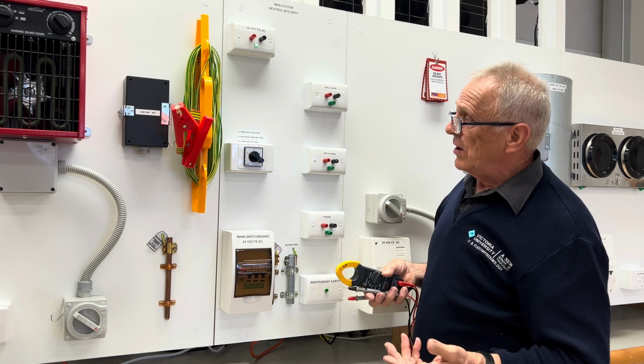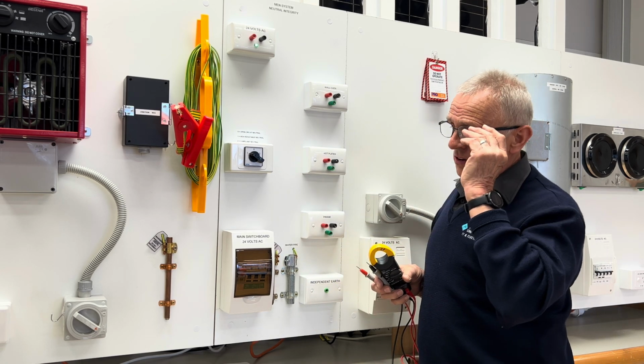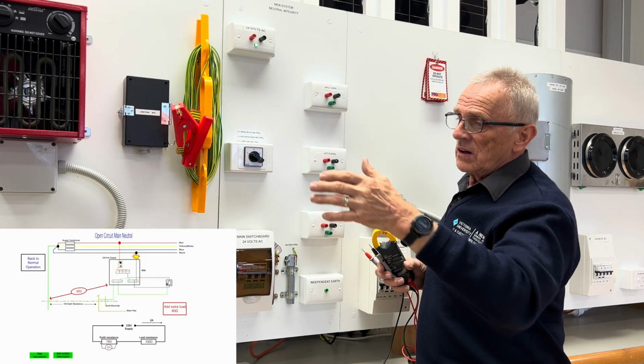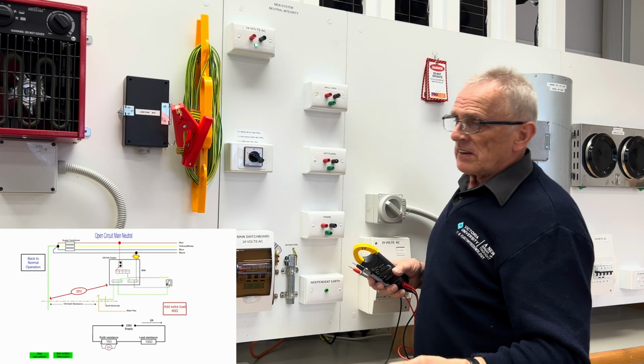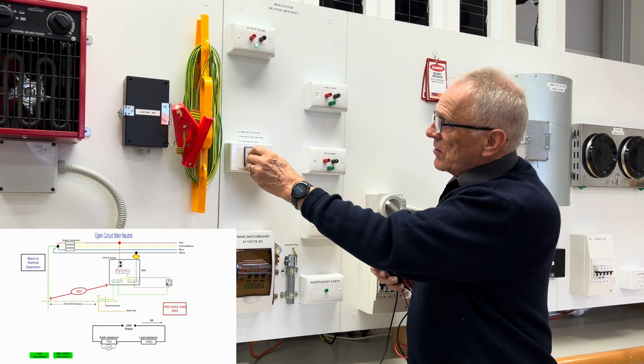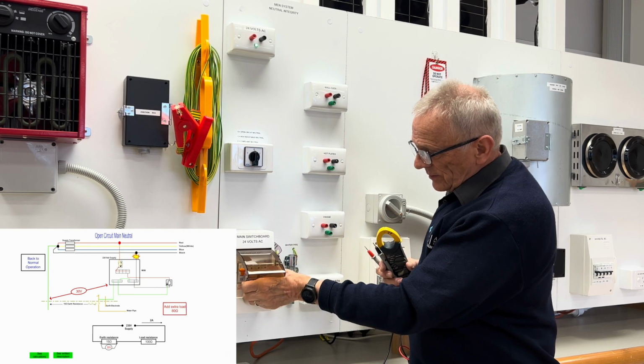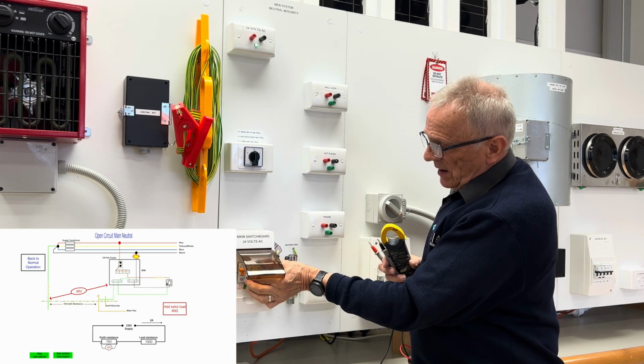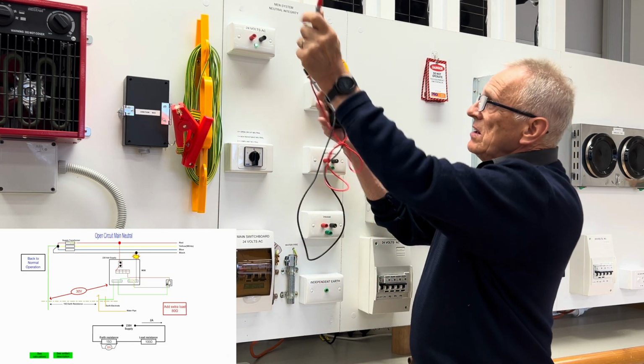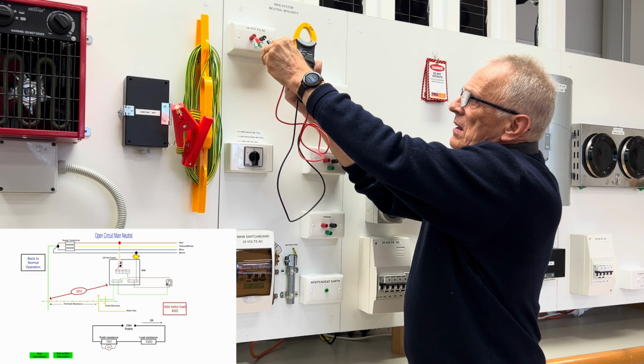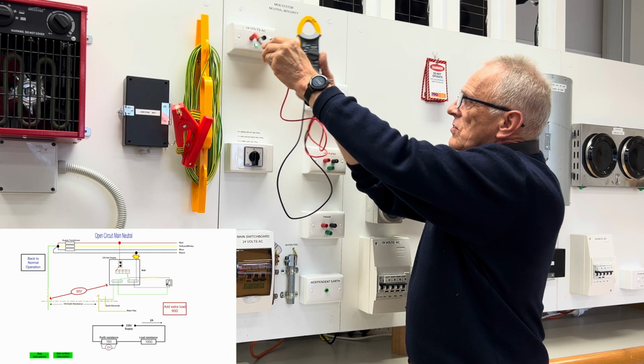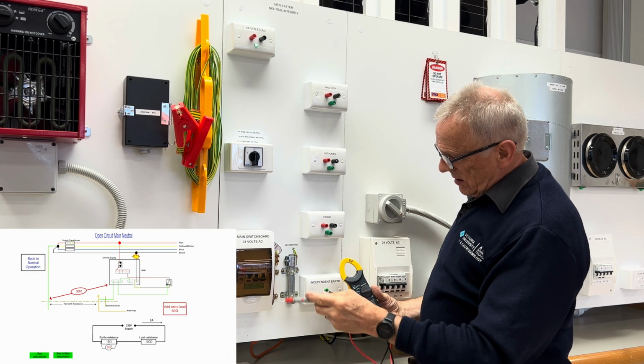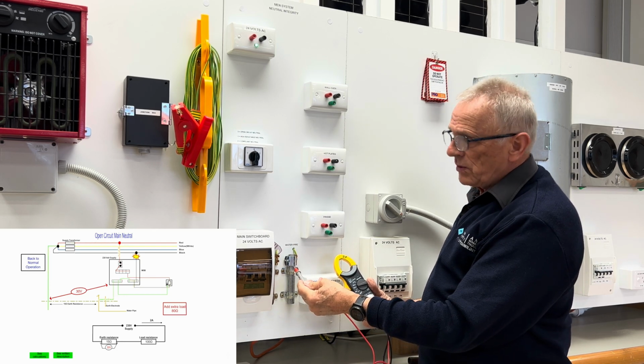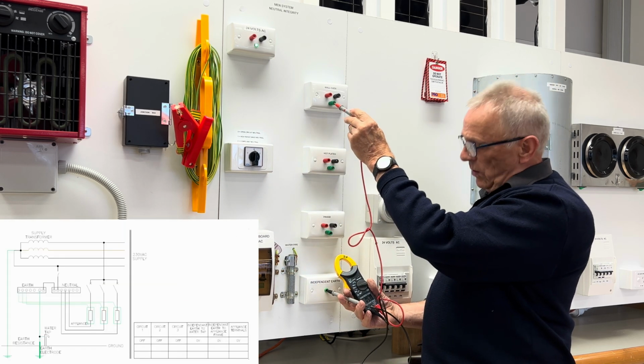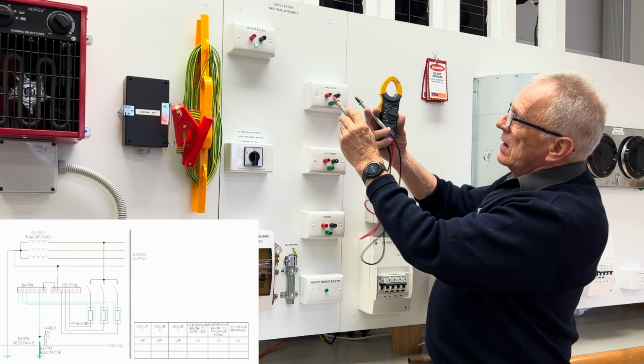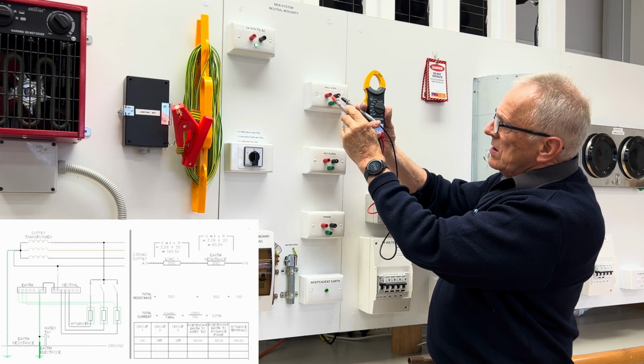So the last scenario is the worst scenario, where we have a total open circuit neutral, where we don't have a neutral at the mains box, broken neutral in the pit, or the service line is totally broken. So if we go now to open circuit neutral, I'll turn these off, and we now test the supply coming in. Still we have our normal supply into the installation. So now independent earth to the water pipe, we're getting 7.5 volts. And we've got the frame of the wall oven, 7.5 volts. Supply across the wall oven is 17 volts.